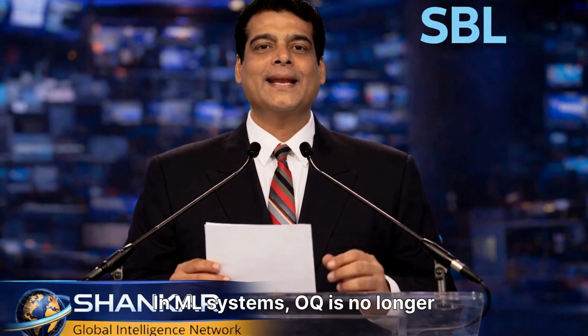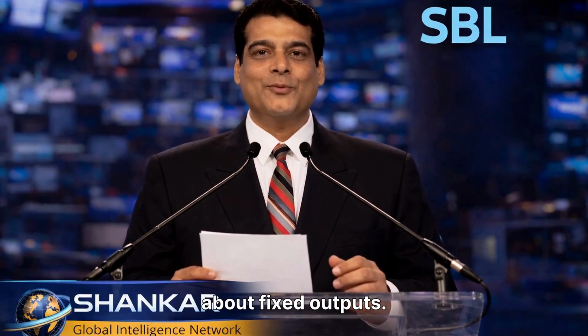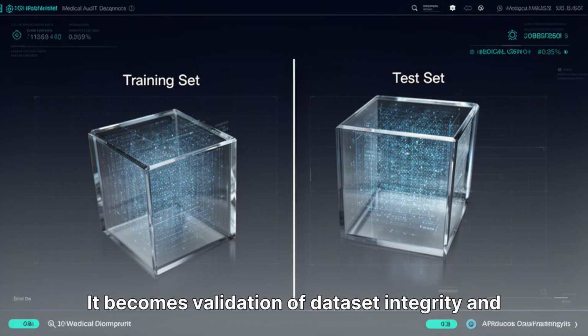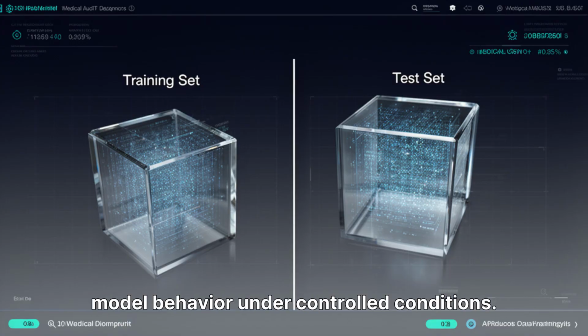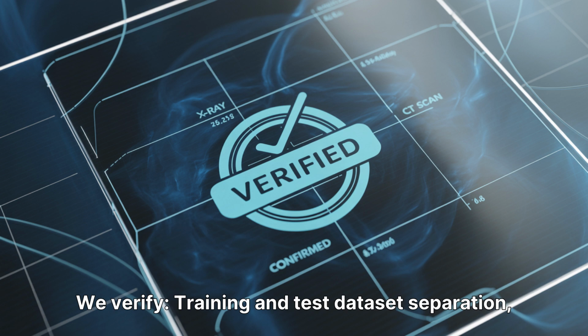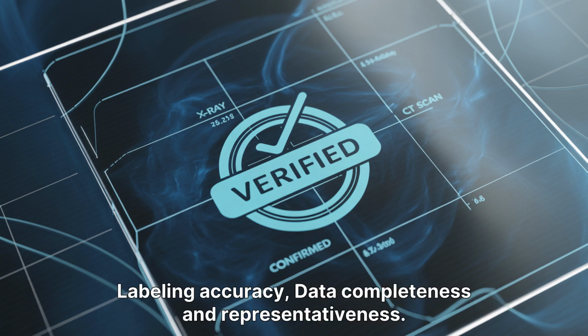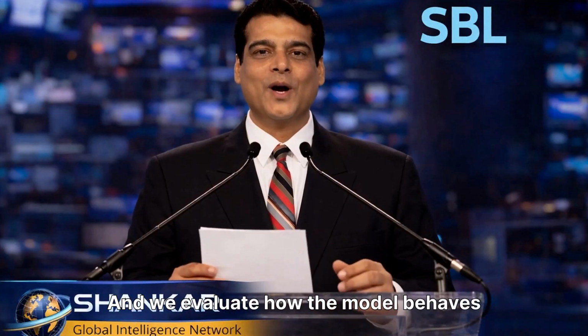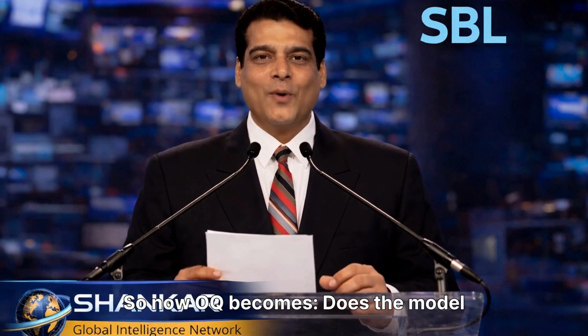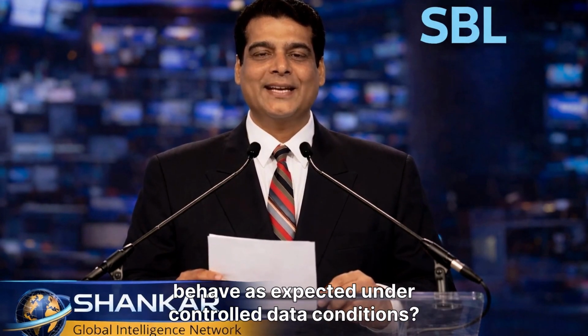Now OQ. In ML systems, OQ is no longer about fixed outputs. It becomes validation of dataset integrity and model behavior under controlled conditions. We verify training and test dataset separation, labeling accuracy, data completeness, and representativeness. And we evaluate how the model behaves on known labeled datasets. So now OQ becomes, does the model behave as expected under controlled data conditions?